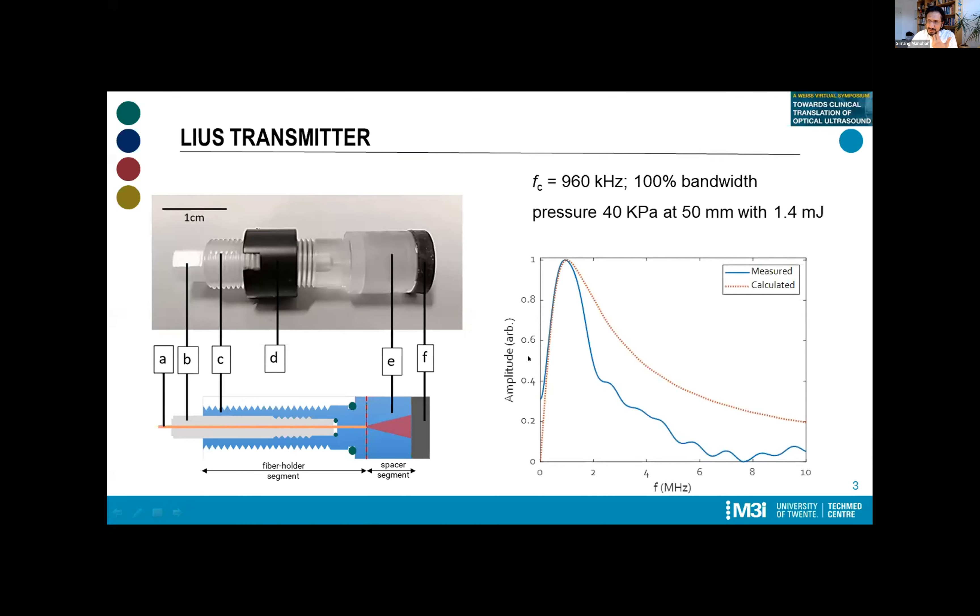What does it look like with actual signals? This is the frequency response. We managed to hit that one megahertz reasonably well with a multitude of such transmitters. The pressures that we can generate is about 40 kilopascal at 50 millimeters in water with about 1.4 millijoules per pulse. The signals are getting to look better and better, but we are still disturbed by this nuisance of a secondary peak that's a reflection of the ultrasound signal at the interface between the spacer segment and the next segment.